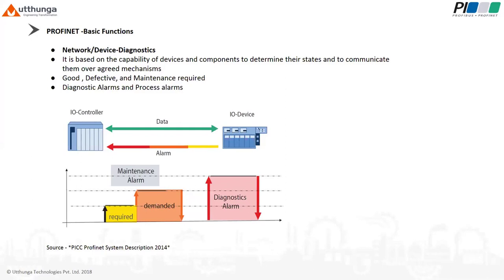A status-based maintenance approach is currently gaining relevance for operation and maintenance. A system for reliable signaling of alarms and status messages by the IO device to the controller was defined for PROFINET IO for this purpose. This alarm concept covers both system-defined events, such as removal and insertion of modules, as well as signaling of faults due to wire break or voltage issues. This is based on a state model that defines good and defective status, as well as maintenance required and maintenance demanded pre-warning levels. In the image, we can see the IO controller talking to the IO device, while the IO device will be sending some information like alarms. The alarm itself is classified into 3: maintenance required alarm, maintenance demanded alarm, and diagnostics alarms.